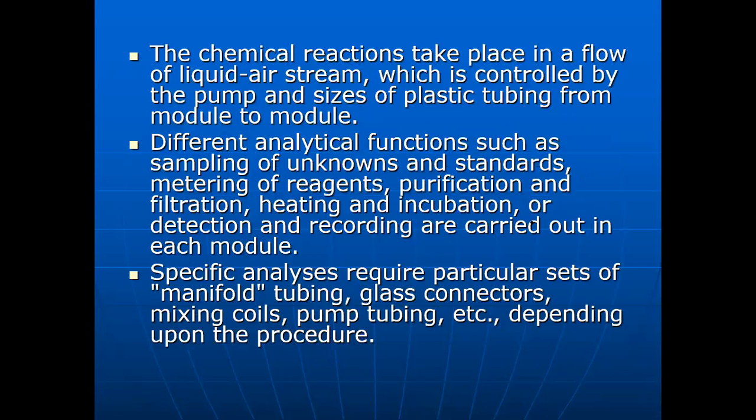Coming to the next point, the chemical reaction takes place in a flowing liquid and air stream, which is controlled by the pump and the size of the plastic tubing from module to module. I will show this in the coming images so that you will completely understand. Different analytical functions, such as handling the sample of unknown and standard materials, reagents, purification, filtering, heating, incubation, or detection and recording, are carried out in each module. So in each module, purification takes place, filtration takes place, and heating and incubation happen. Specific analysis requires particular sets of manifold tubing, glass connectors, mixing coil, pump tubing, etc.